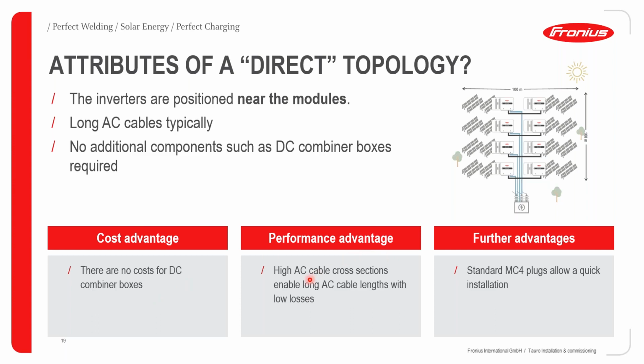And then the performance: because of the higher AC cable cross sections that are possible with the V clamps, you can go for much longer distances with minimal power losses. And this is how the Tauro affects the total power losses in your system. The V clamps provided on the AC side can accommodate cable sizes of up to 240 millimeters square, and that also has a huge impact on your design flexibility as far as the distances that you can cover are concerned.